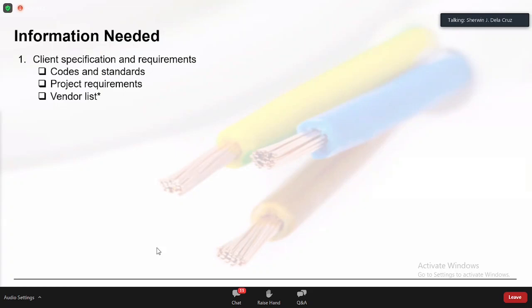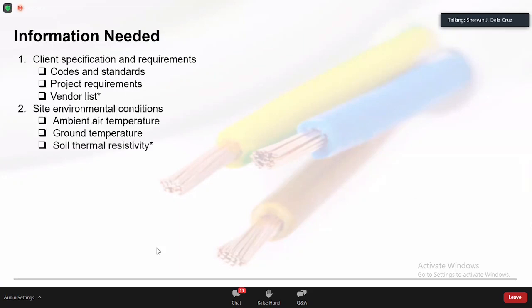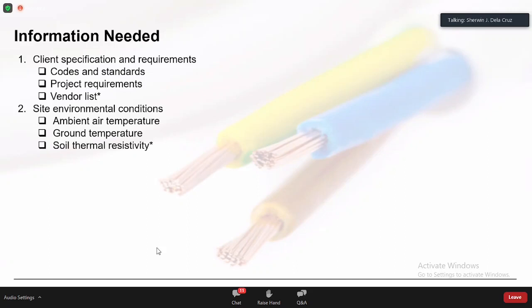The next design inputs are the site environmental conditions: air temperature, ground temperature, and soil thermal resistivity. Temperature values are usually specified in the client specs and easy to identify. In the Middle East, the maximum site condition is often 50 degrees Celsius and above. Soil thermal resistivity is determined during detail engineering design by hiring a subcontractor to test the soil — that gives you the exact soil thermal resistivity value.